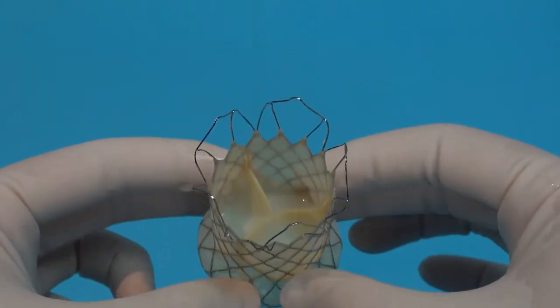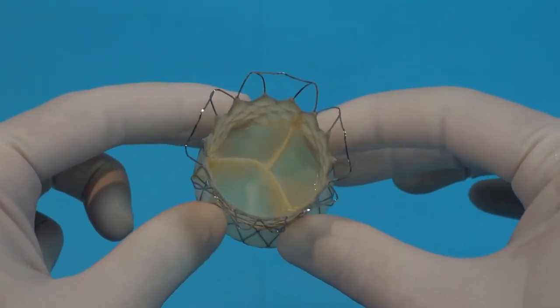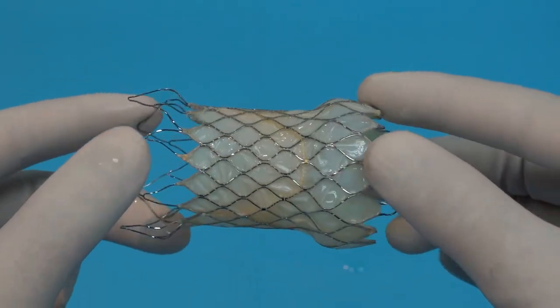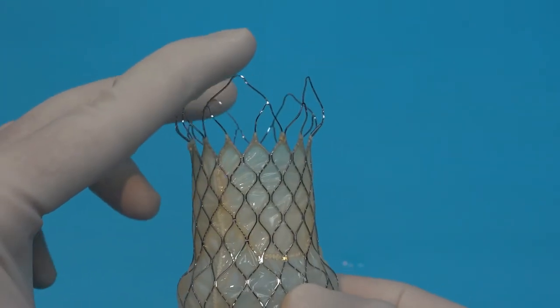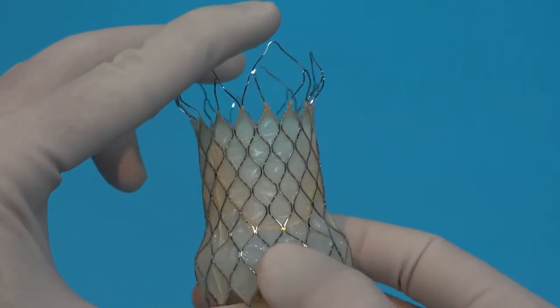I will talk about the delivery system much later. Let's have a close-up view on the Venus P-valve. The entire nitinol support frame is covered with porcine pericardial tissue with the exception of the distal cells or outflow flare.